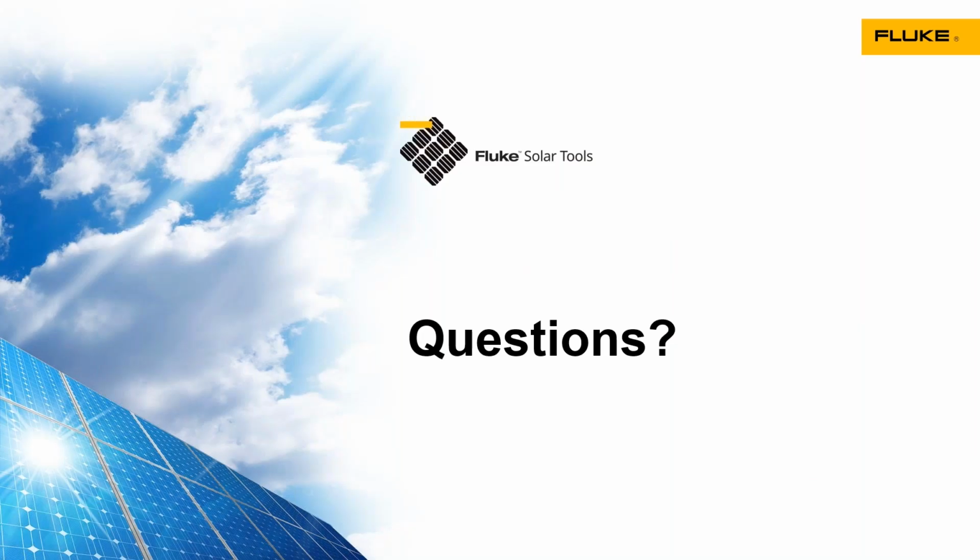The GFL 1500 will do the analysis to see if there's voltage to ground, which if the fault is active, it will. It may show a high resistance reading there, but you'll know there's a fault there. You can use the fault function to figure out where the fault is located. You may have trouble tracing it because high resistance faults may not have the ability to pass much current. And so using the low signal mode, using array mode, and using the band pass filter with the signal tracing clamp are all techniques you can use to find an intermittent ground fault.